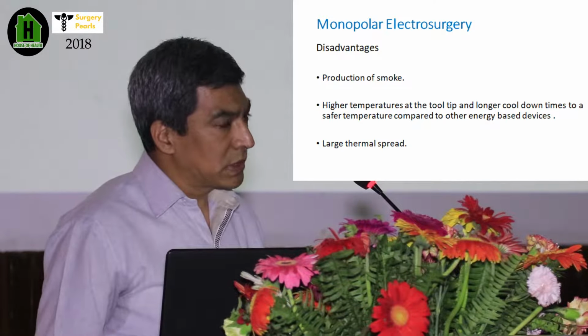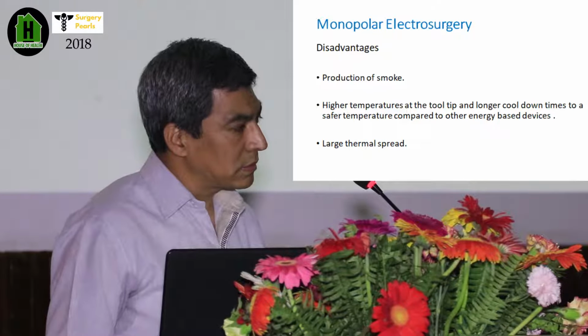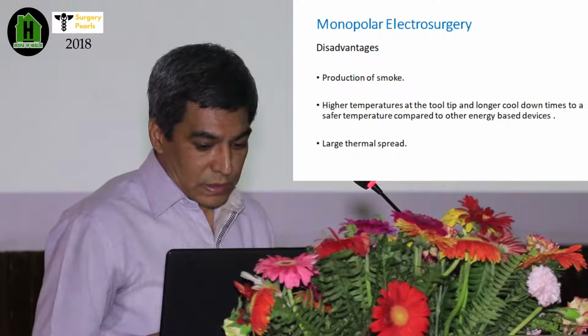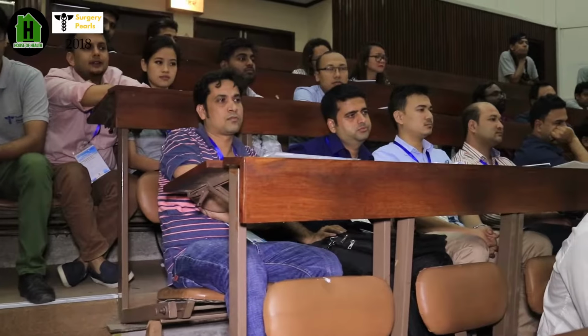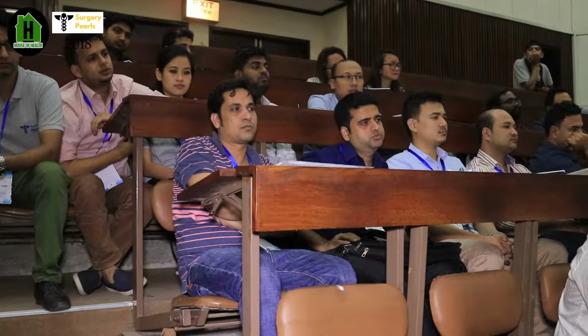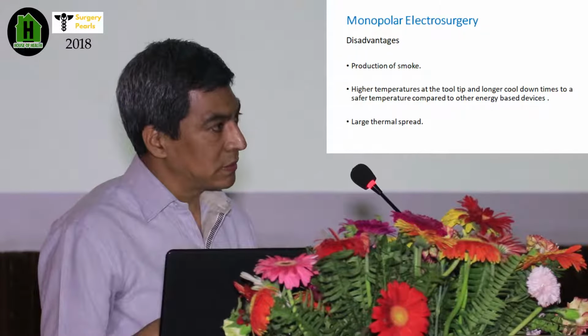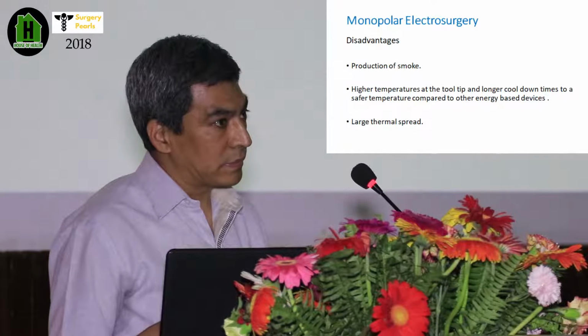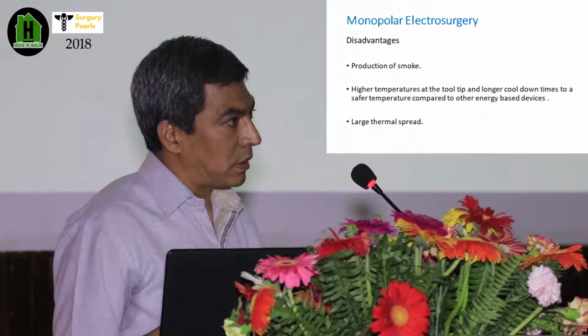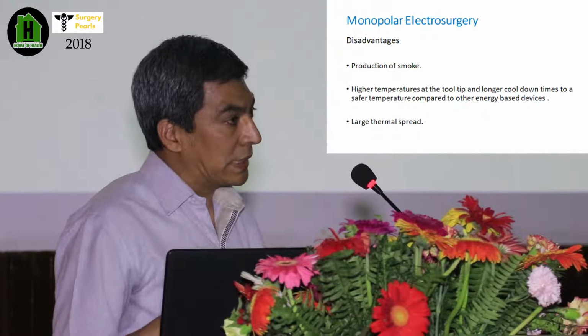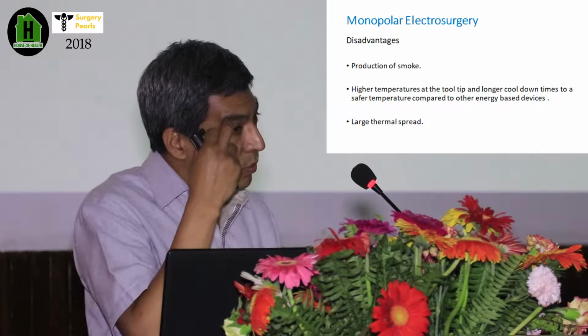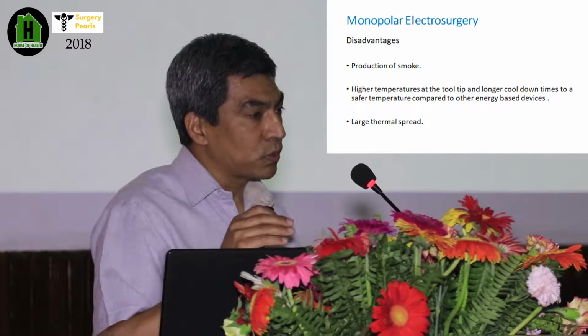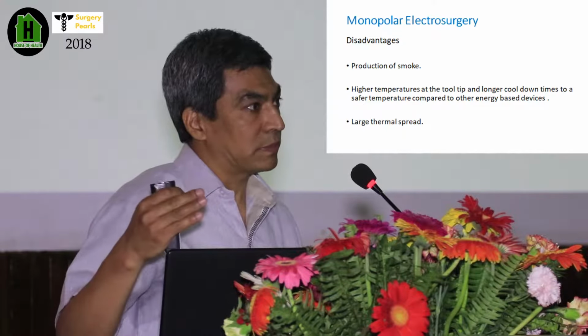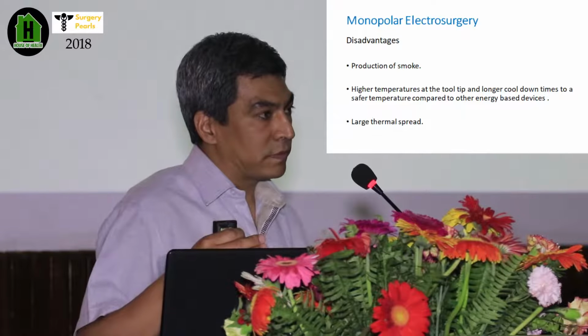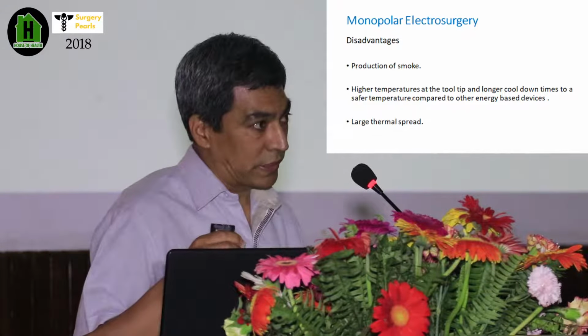It gives a significant amount of smoke, which hinders our operating field. And the high temperature at the tip of the active electrode is another disadvantage of this equipment, because it won't cool immediately, unlike the ultrasound. So it keeps on heating for a long time. If you leave those cartridges unattended, it might cause problems again. And the thermal effect of this monopolar is very high. You won't know up to which level the thermal effect has transmitted from the point of generation, the point of starting.